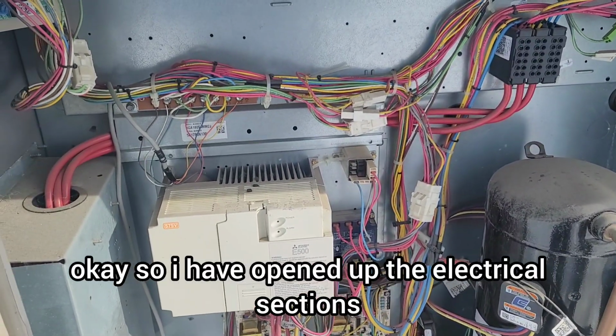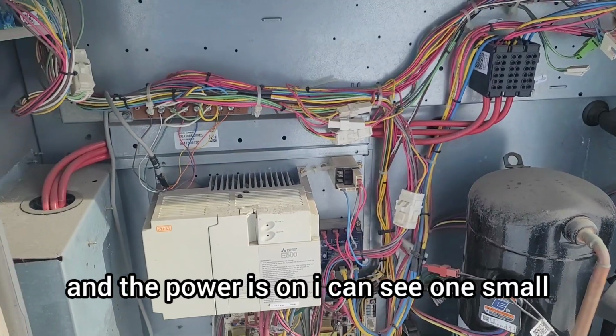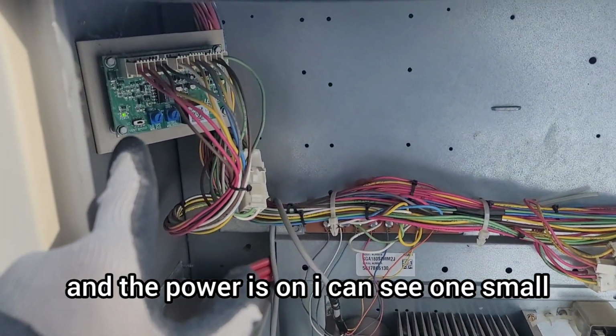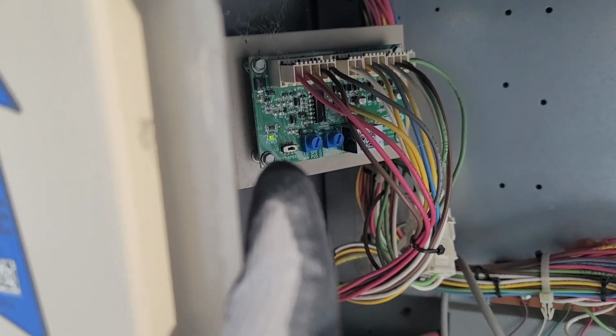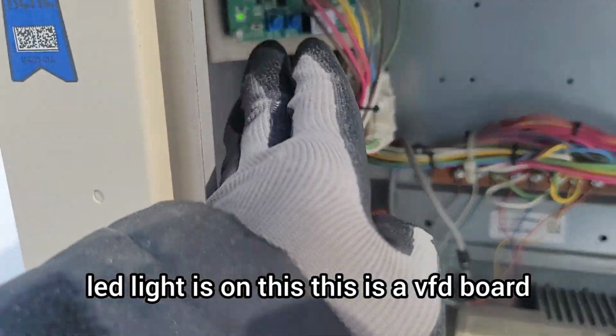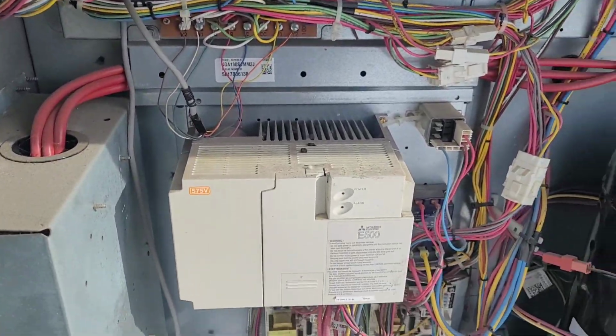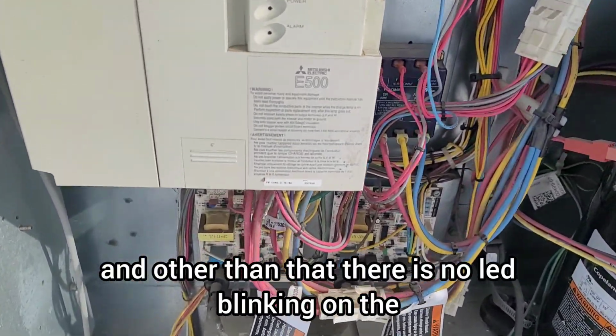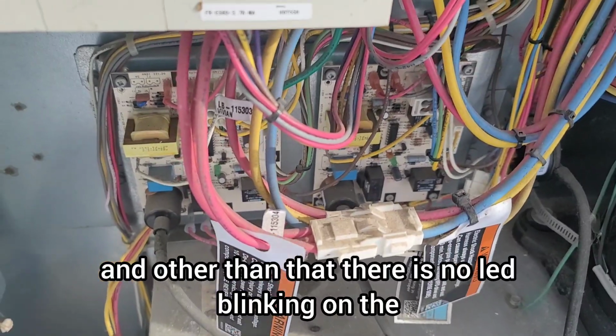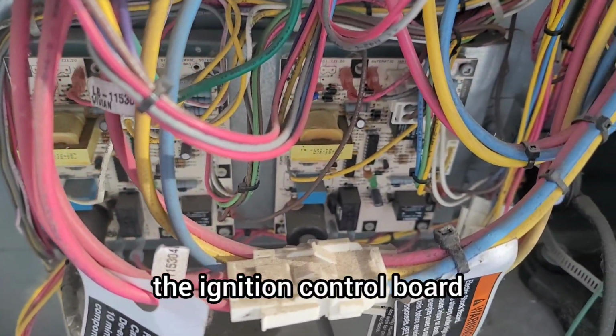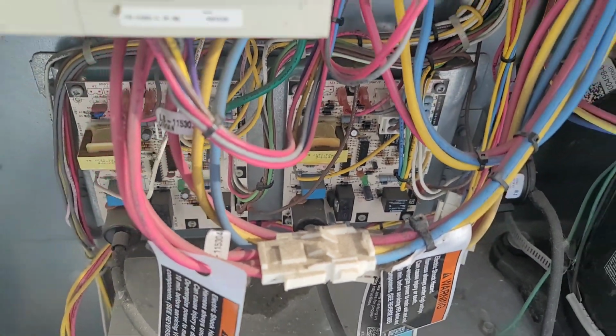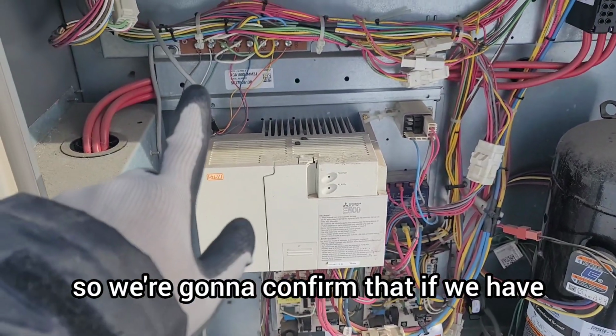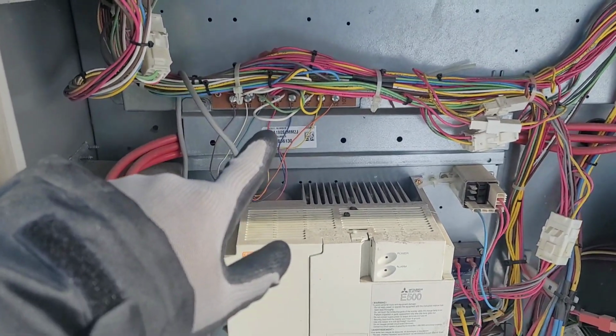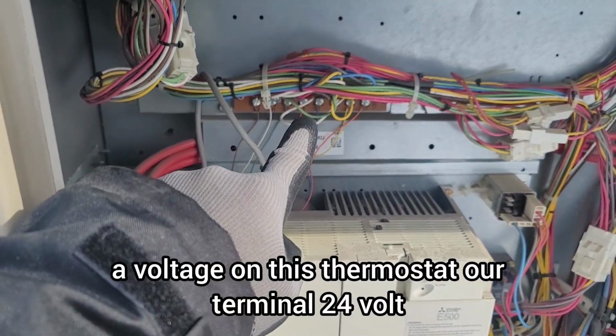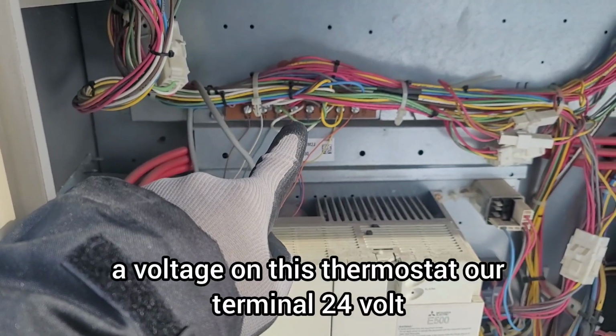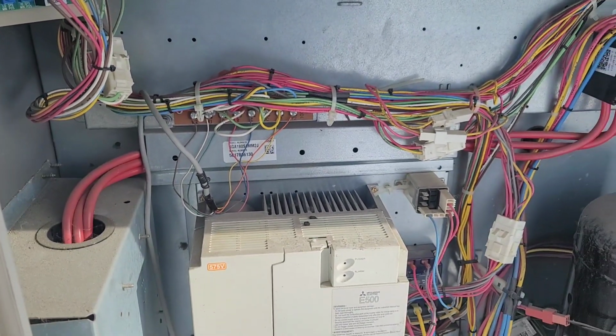Okay, so I have opened up the electrical sections and the power is on. I can see one small LED light is on. This is the VFD board, and other than that there is no LED blinking on the ignition control board. So we're gonna confirm if we have voltage on this thermostat R terminal, 24 volt, first.